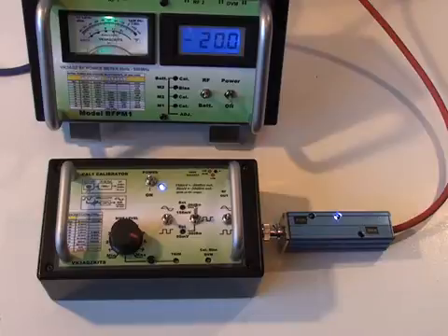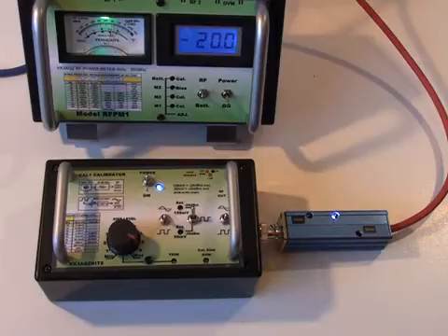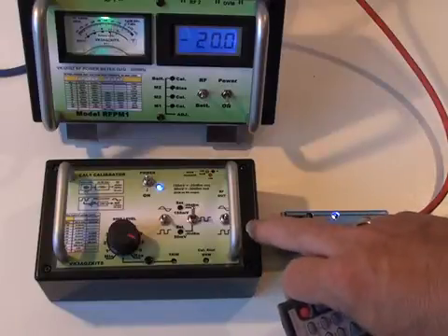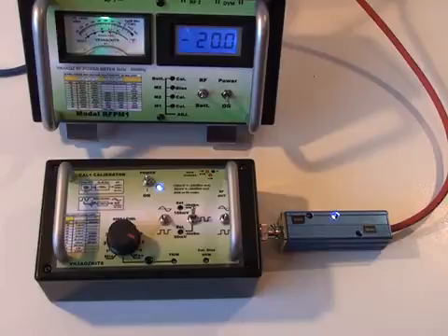Now, a square wave peak-to-peak signal can be measured with a digital voltmeter if you feed the square wave into an integrator. So you can set the output of this calibrator quite accurately using an accurate digital voltmeter.